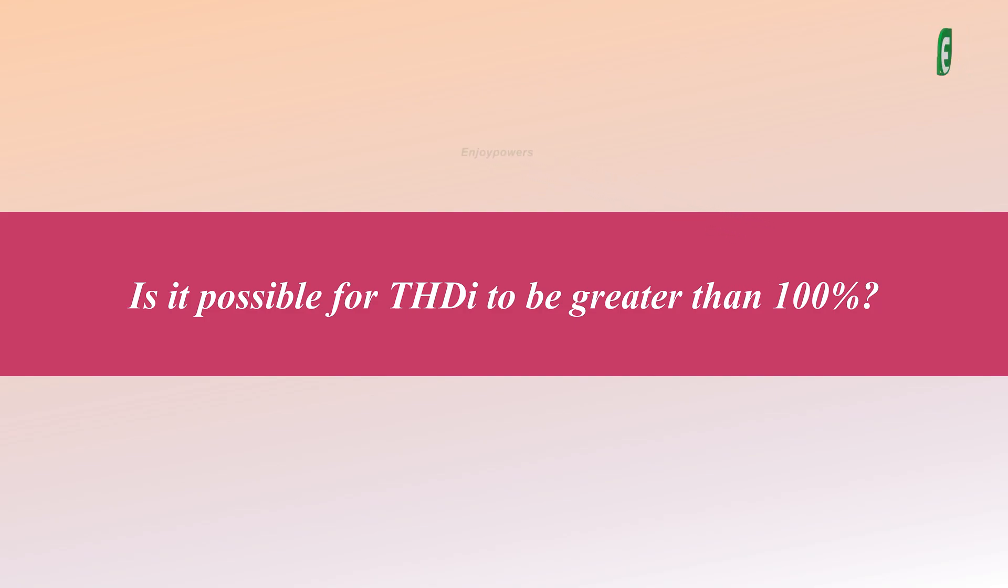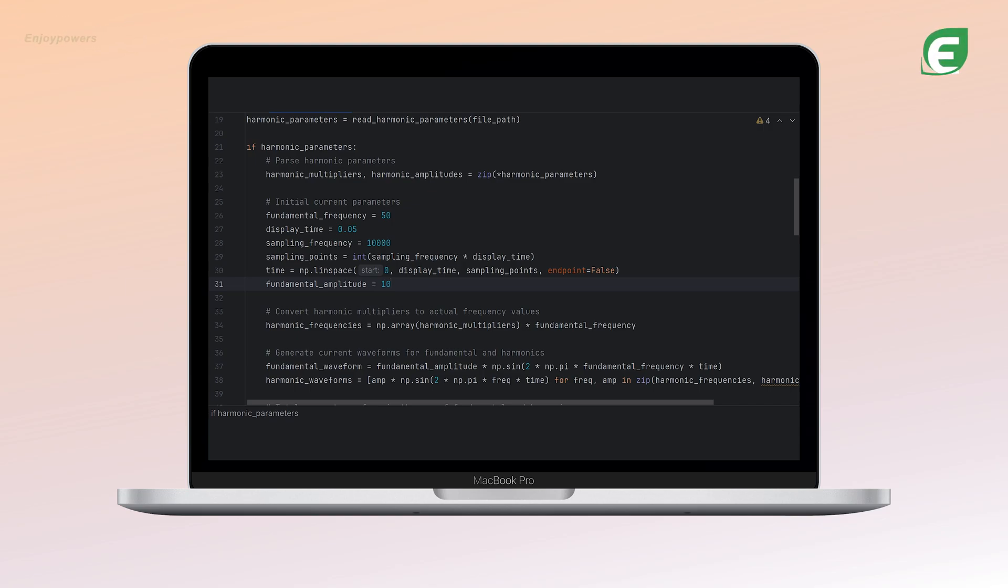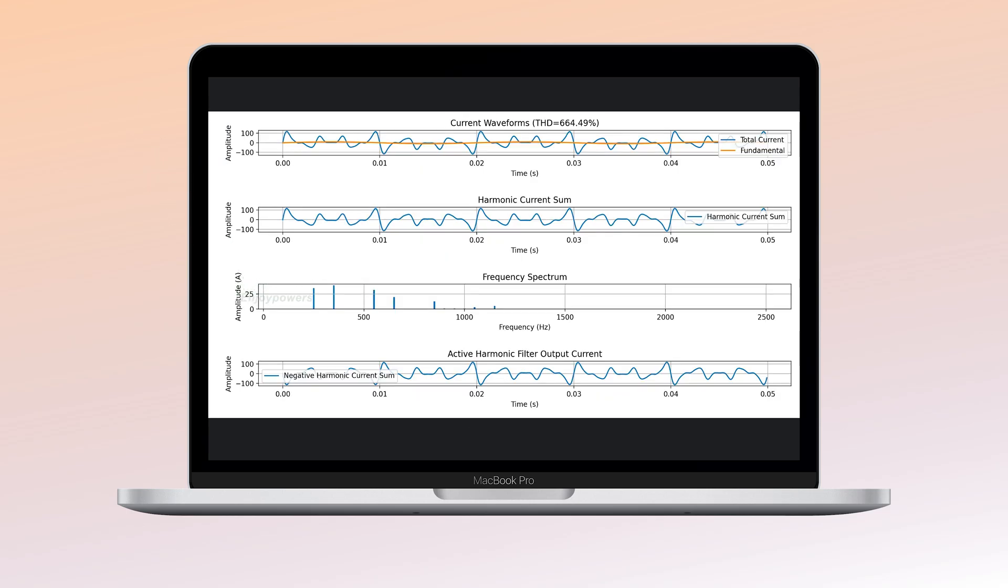The answer is yes. THD can exceed 100%, especially when the fundamental current decreases. For example, if we reduce the amplitude of the fundamental current from 100A to 10A, the THD value becomes 664%, indicating that THD can indeed be greater than 1.